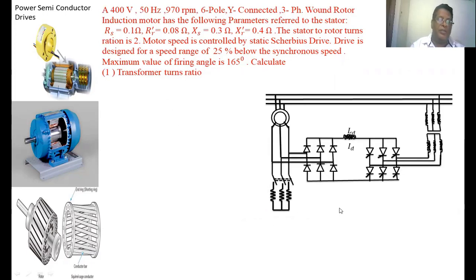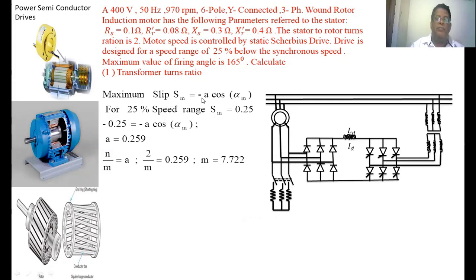We know this is the circuit diagram for the Scherbius drive. Maximum slip Sm = -a·cos(αm). The speed range is 25%, so slip for the induction motor is 0.25. Substituting the values, we get a = 0.259, where a = n/m. Here n is the stator to rotor turns ratio of the induction motor, and m is the primary to secondary turns ratio of the transformer. Given n = 2, substituting that value, we calculate m = 7.722.